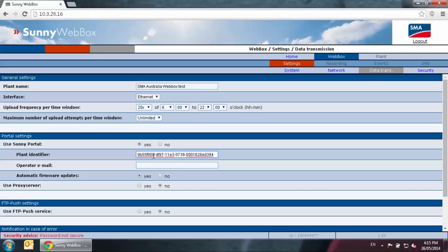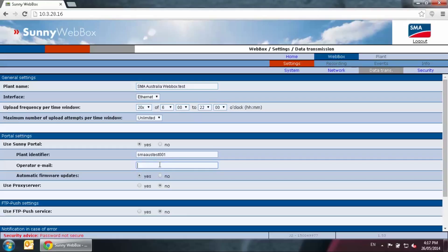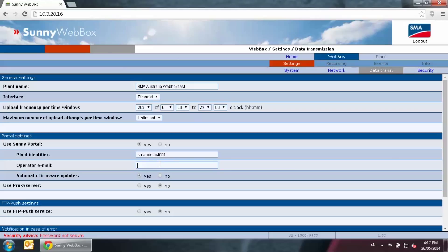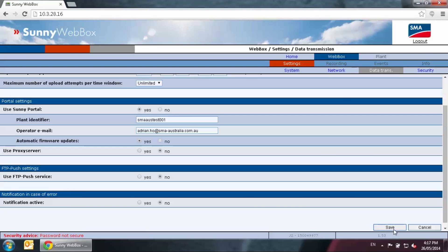Plant identifier is the fingerprint for the web box. When you perform a full factory reset, it will give itself a new plant ID. To avoid clashing with another web box that is already registered in Sunny Portal, just simply delete this field and type something unique. Let's say your job number. Here we will put in SMA AUS test 001. The operator email is the email where Sunny Portal will send the activation email. If you are an installer, you should be putting the company's support email address so it will have all the registered sites under the same email. When the web box is registered online, you can then add the client's email or the IT staff email address through Sunny Portal. Here I will use my email address. If the site has proxy server settings, you can also change it here. For our test case here, we don't have any. When everything is done, you can press save.